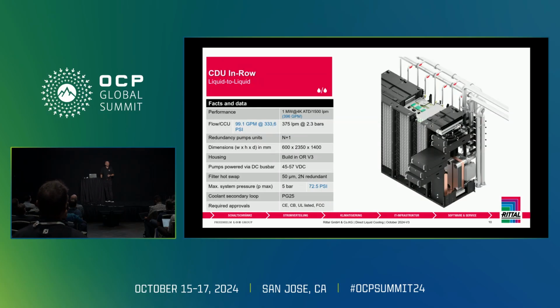Some facts and figures around it. I've already said 1 megawatt at a 4K approach temperature delta. N+1, built on ORV3. Everything within it is powered off the 48 volt backplane at the back. So whether it's, of course, the standard OCP components, the power shelves, the BBUs, all come off the bus bars, but so do all of our CCUs and our CDUs. And they all slide in and are powered off that 48 volt nominal bus bar.